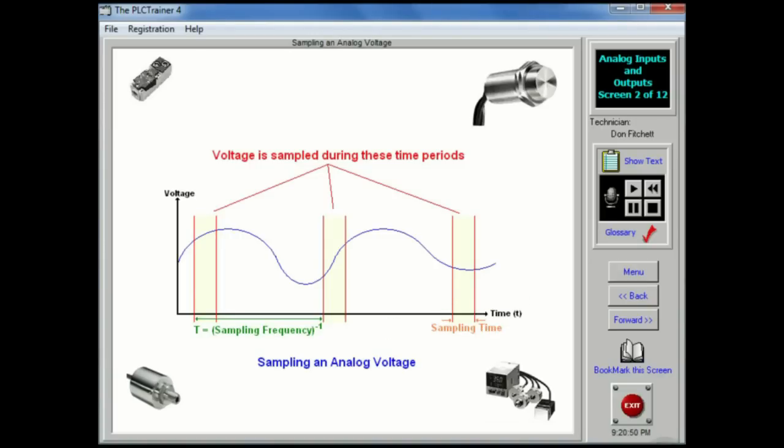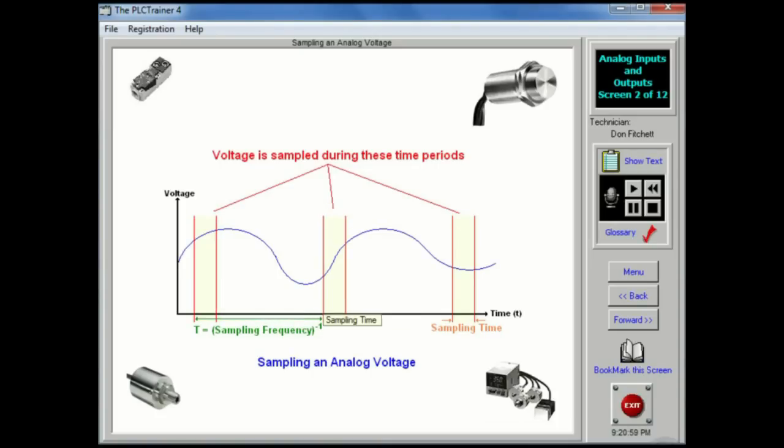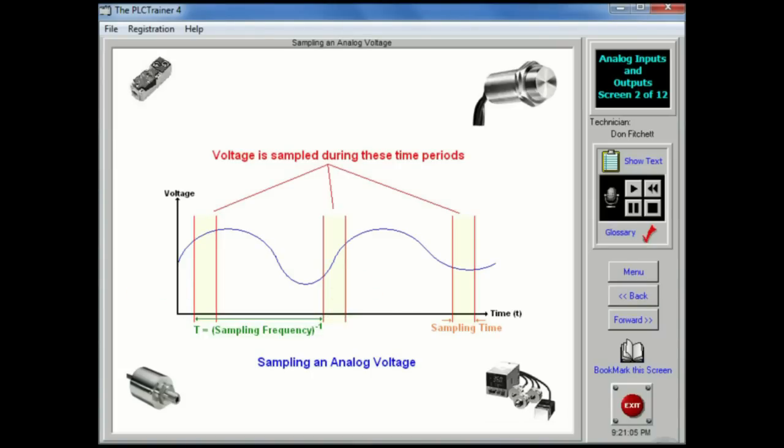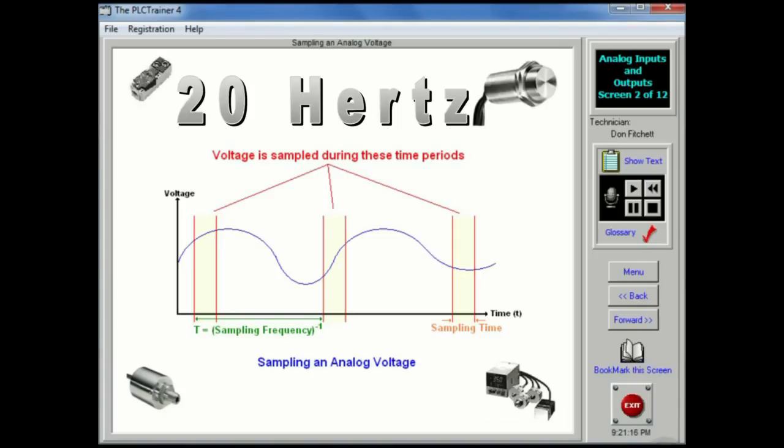AD converters can only acquire a limited number of samples per second. The time between samples is called the sampling period, T. And the inverse of the sampling period is the sampling frequency, also called the sampling rate. The sampling time is often much smaller than the sampling period. The sampling frequency is specified when buying hardware, but for a typical PLC, a maximum sampling rate might be 20 Hz.